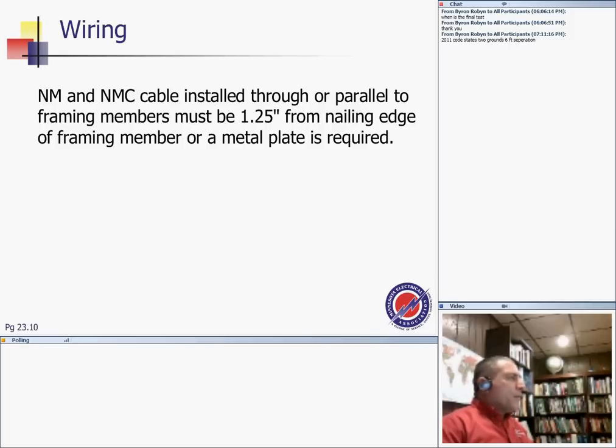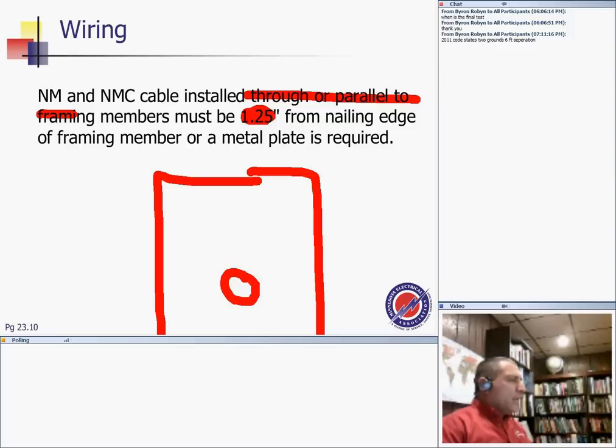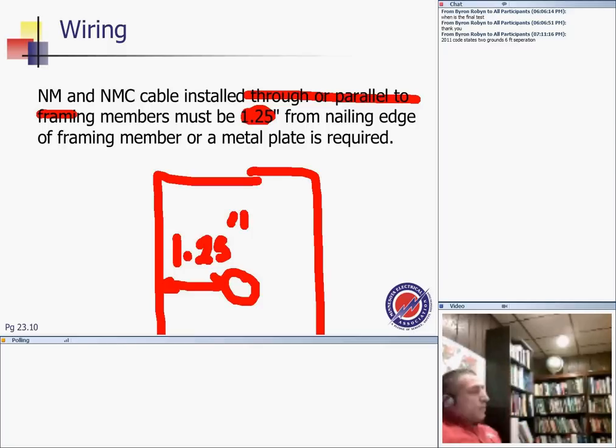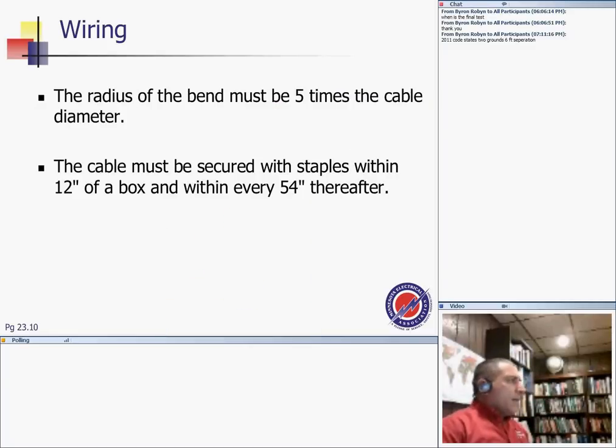Wiring, guys, we all know if you're going to install through or parallel to framing, you have to maintain 1.25 inches. You guys remember we talked about this when we talked about wiring a long time ago. That's for the sheetrocker, so the screws can't cut through that cable. Bend, and this is just a quick review, guys, since we talk about residential. You can't bend it less than 5 times the diameter, because that will damage the insulation. It must be secured. When you secure, guys, we have to secure within 12 inches of the box and every 4.5 feet.